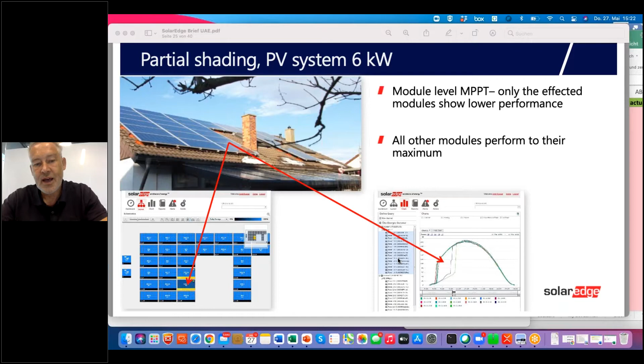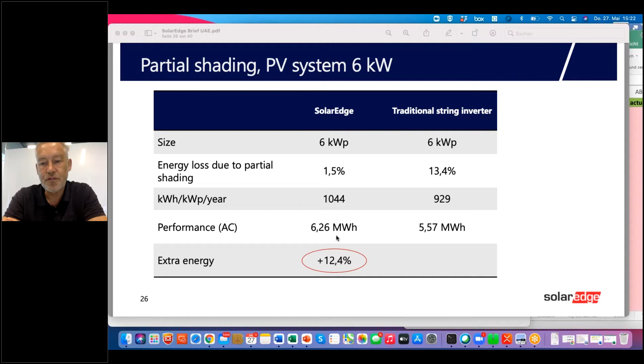But look what happens when you use SolarEdge. These 2 panels are affected, but only these 2 panels are affected. That's why we give these 2 panels individual control. The other panels perform absolutely to their maximum; they are not affected during this partial shading. That gives us higher yield. In this specific case, we would end up with 12.4% more energy yield, and this makes a big difference in the return on investment of a system.